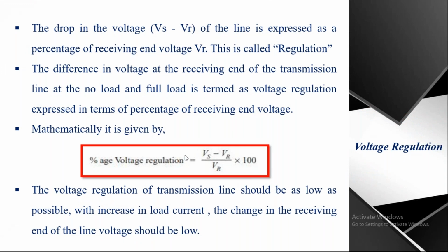Now the formula for percentage voltage regulation is given by Vs minus Vr divided by Vr into 100. This can also be represented as no load voltage minus full load voltage divided by full load voltage into 100. The voltage regulation of a transmission line should be as low as possible - lower regulation means we can achieve better performance from the transmission line.